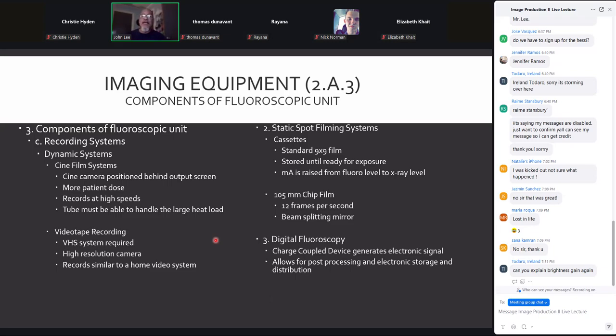The tubes had to be capable of handling the large heat load for all of the exposures that were made in such rapid succession. The other option was to couple the television camera tube, put an output on it to a VCR. So we could use VHS systems, high resolution cameras to record the studies. Our static methods included the spot film, which used cassettes. They were actually put into the tower and moved out of the way and held in a shroud, protected from radiation until they were needed.